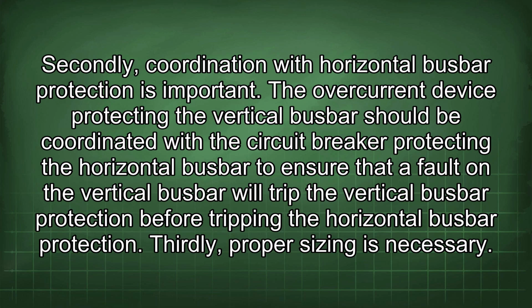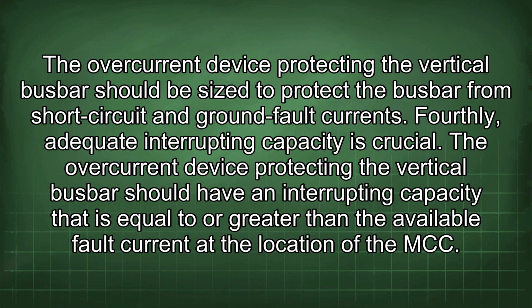Thirdly, proper sizing is necessary. The overcurrent device protecting the vertical busbar should be sized to protect the busbar from short circuit and ground fault currents. Fourthly, adequate interrupting capacity is crucial. The overcurrent device protecting the vertical busbar should have an interrupting capacity that is equal to or greater than the available fault current at the location of the MCC.